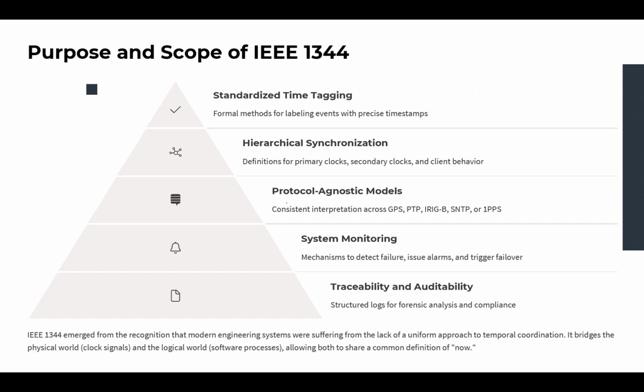Now that we've seen what happens when we don't have synchronization in time, let's talk about the central solution that IEEE 1344 basically proposed. This standard, which is a standard for synchronization, measurement, and control systems, does not define a specific protocol. You have to note that, but it defines a framework, and that framework can be applied to a diverse variety of fields, industries, and systems. The goal is to ensure temporal integrity. So we have a synchronized time, we can trace the events, and we have system-wide consistency.